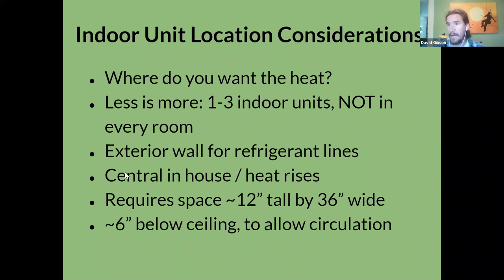As a heat pump designer working for Revision Energy for the last 3 years, we had a lot of customers that were like, oh, we want one in every bedroom and we want one in the kitchen and we want one in the dining room. And no, you don't. You want them to be able to distribute the heat and blow air around, and generally you wouldn't want to mount one in a room that's smaller than about 10 by 10 or 12 by 12. A smaller bedroom is going to be too small. They can have trouble maintaining the temperature if the space is too small.